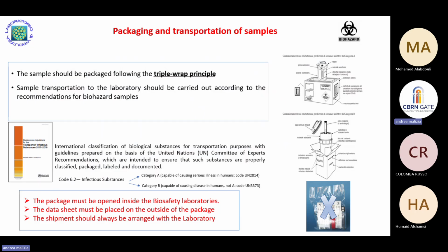Instead, if the laboratory staff, when the sample arrives, is really confirmed as a BSL4 pathogen, you open it mandatorily in a BSL4. For example, a person that arrived with Ebola infection, I open in BSL4. But a suspect case of hemorrhagic fever, I can open in BSL3. It's in line with the guideline of international procedure.